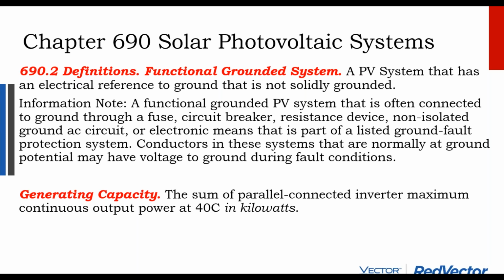What this term is really here for is that we've had a change in inverter architecture, whereas more traditional, like early 2000s and earlier solar inverters were, and most battery inverters on the market today are negatively grounded inverters. And what that means is on the DC side, they would take the negative side and tie it directly to ground, and that makes sure that your DC side, you have a positive side and you have a negative side. And so on that negative side, they would ground connect it directly to ground and keep it pegged at that 0 voltage ground potential.